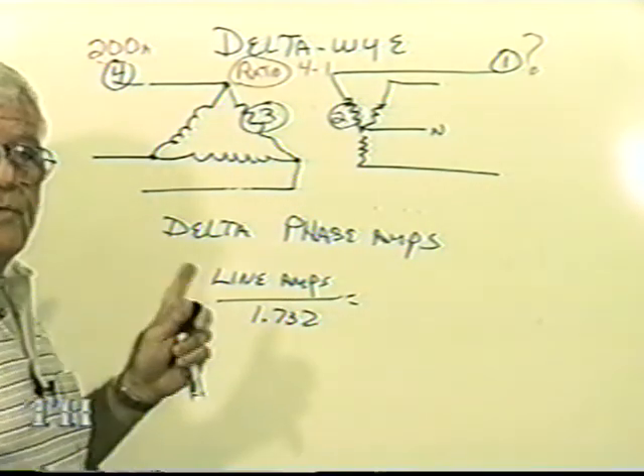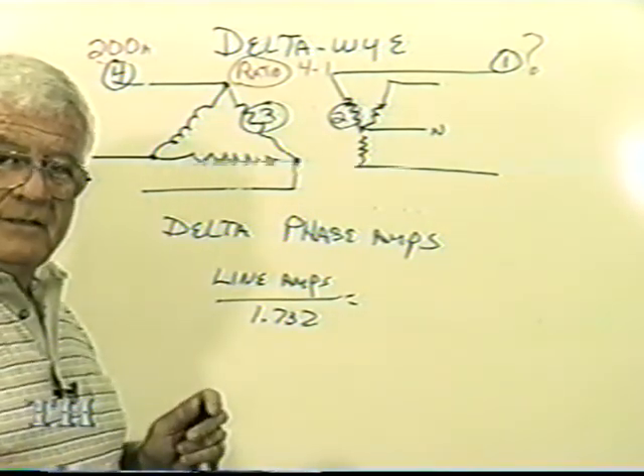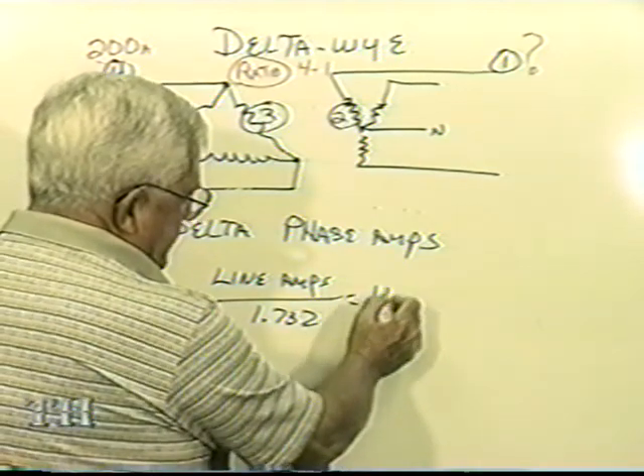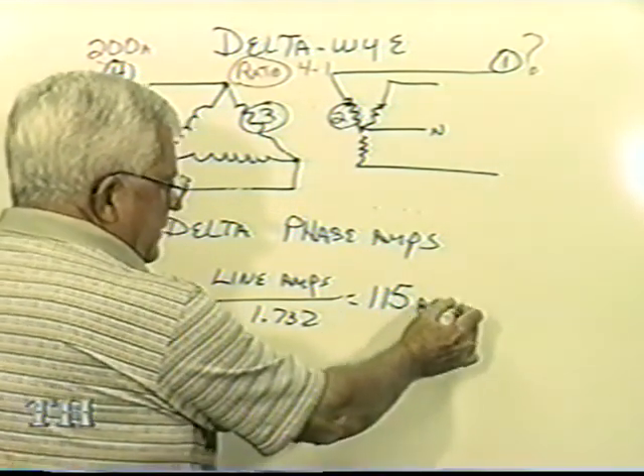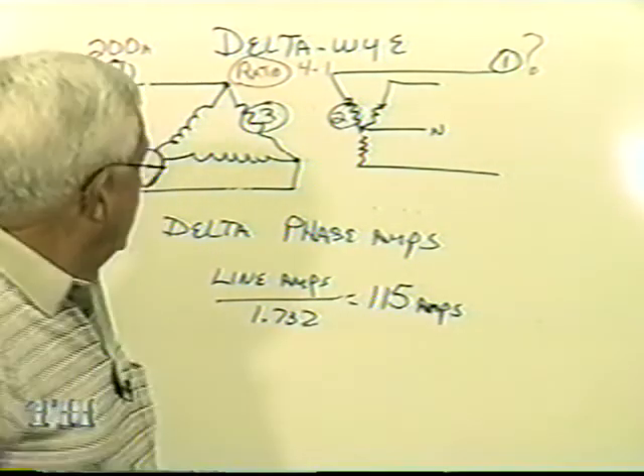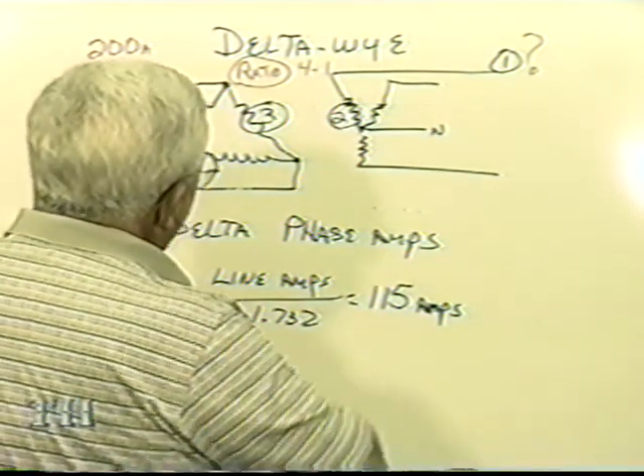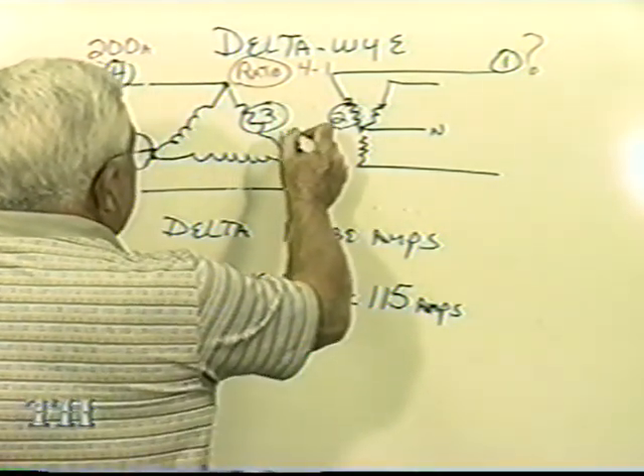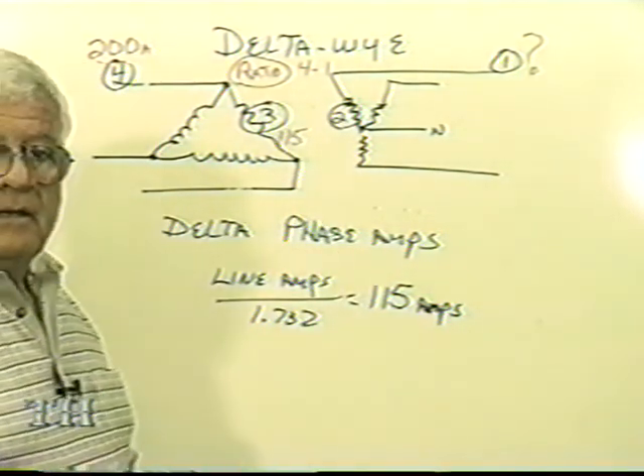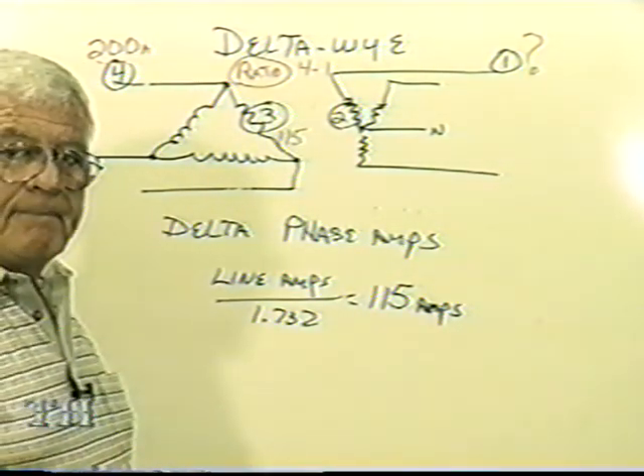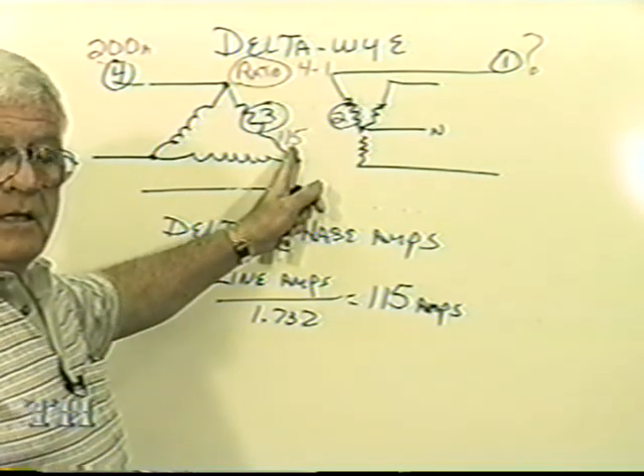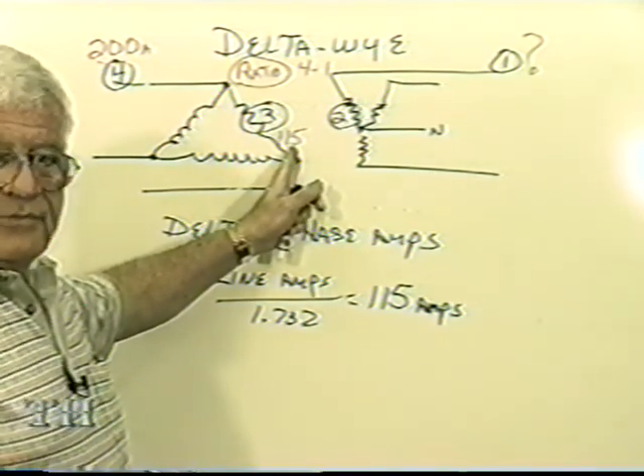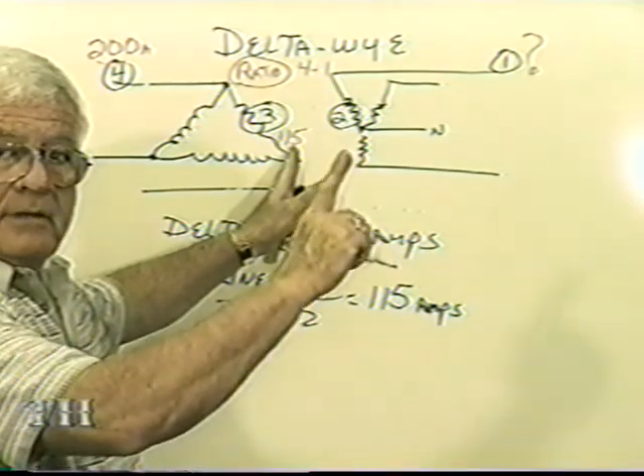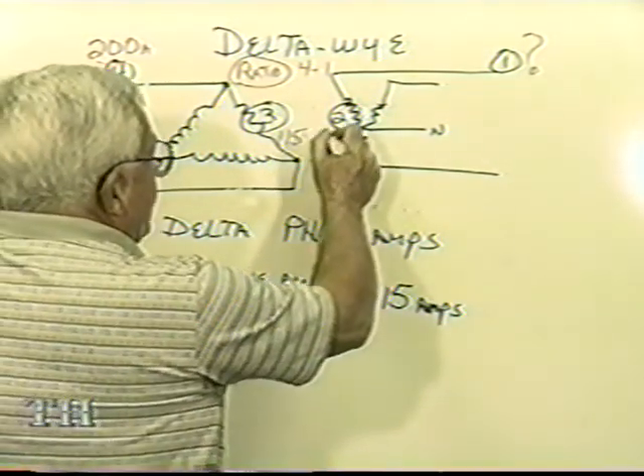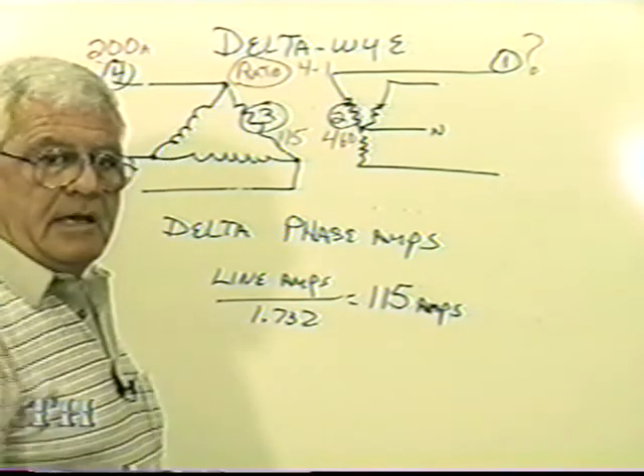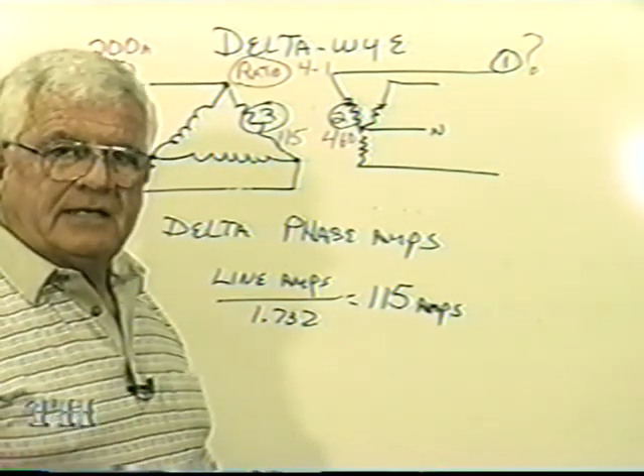So if I took 200 amps and divided it, you should be looking at approximately 115 amps. So you come over here right now and write down 115 amps. Now do you see that ratio? What's going to happen to this if I lower the voltage 4 times? This is going to go up 4 times to what? 460? At position 2, I have 460 amps.